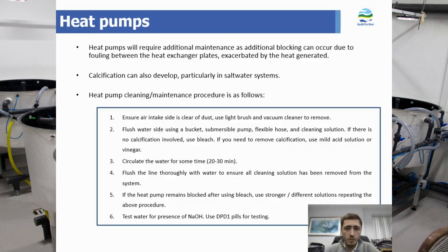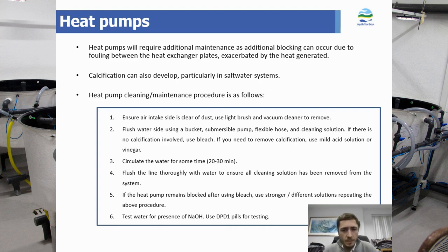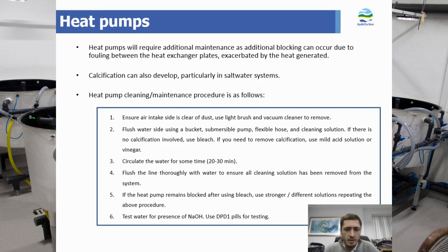So, heat pumps. Heat pumps require a bit of additional maintenance because of the fouling that can occur within the heat exchangers and also due to the heat generated by the heater itself or the incoming warm water it's trying to cool down. The decalcification procedure is very similar — we have the option of swapping out the cleaning solution similarly. The additional maintenance is more just cleaning. There is more dust entering a heat pump, so we want to ensure that the air intake sides are clear of dust and that the radiator plates on the back are clear as well.